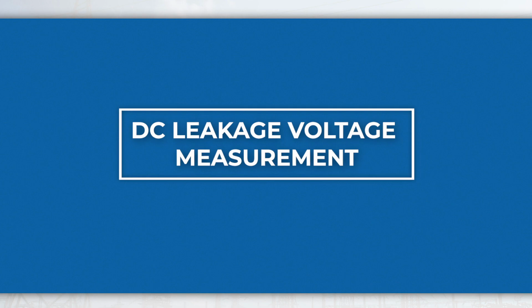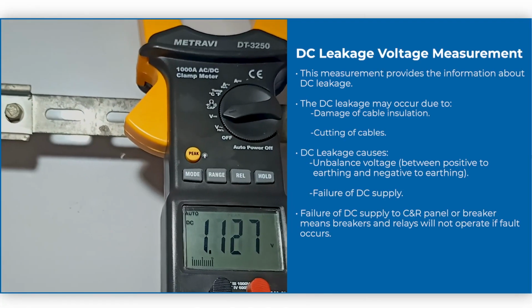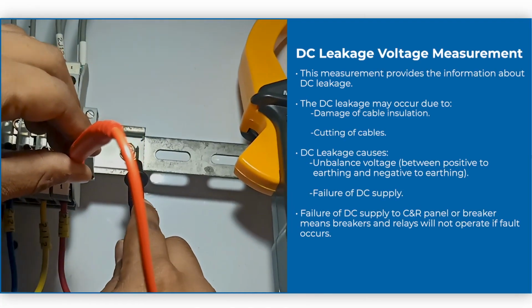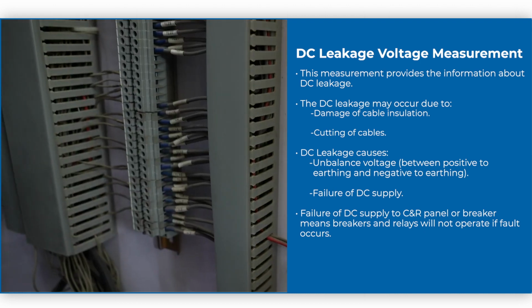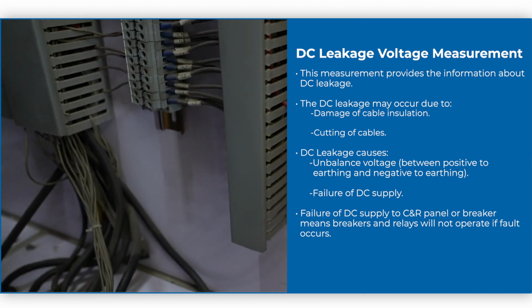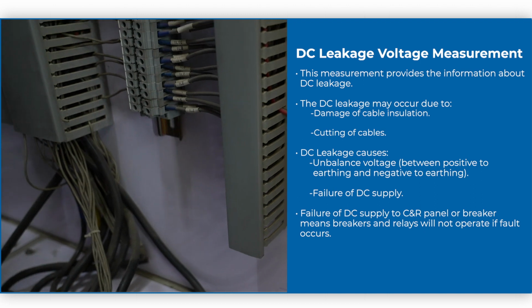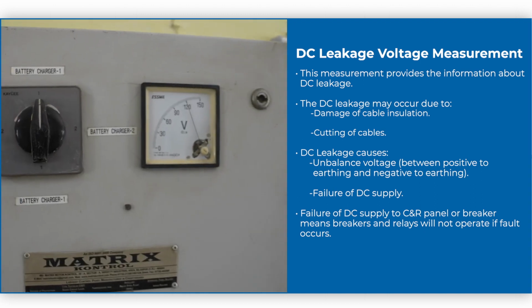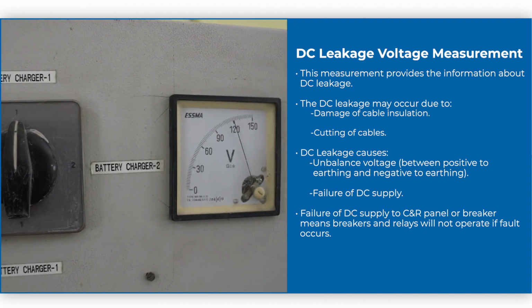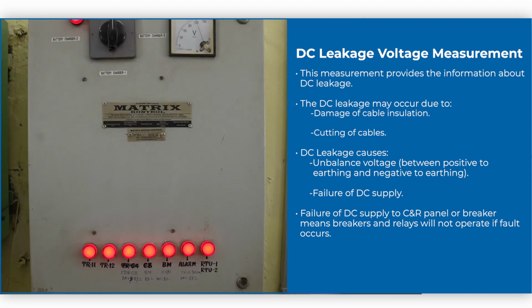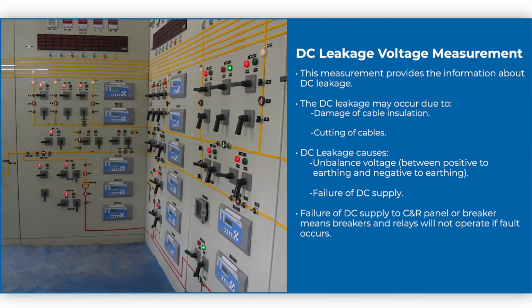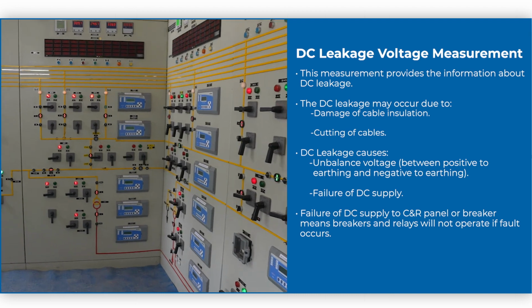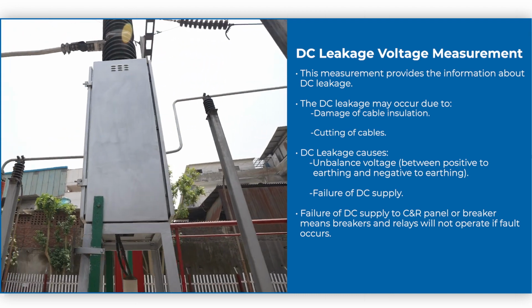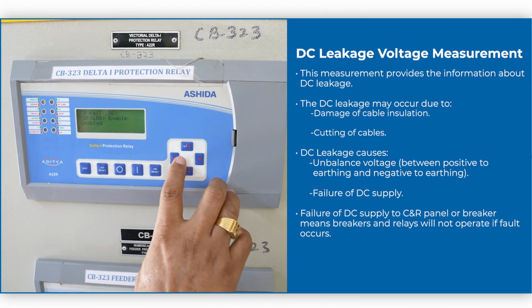DC leakage voltage measurement. This measurement provides the information about DC leakage. The DC leakage may occur due to damage of cable insulation and cutting of cables. DC leakage causes unbalanced voltage and failure of DC supply. Failure of DC supply to C&R panel or breaker means breakers and relays will not operate if fault occurs.